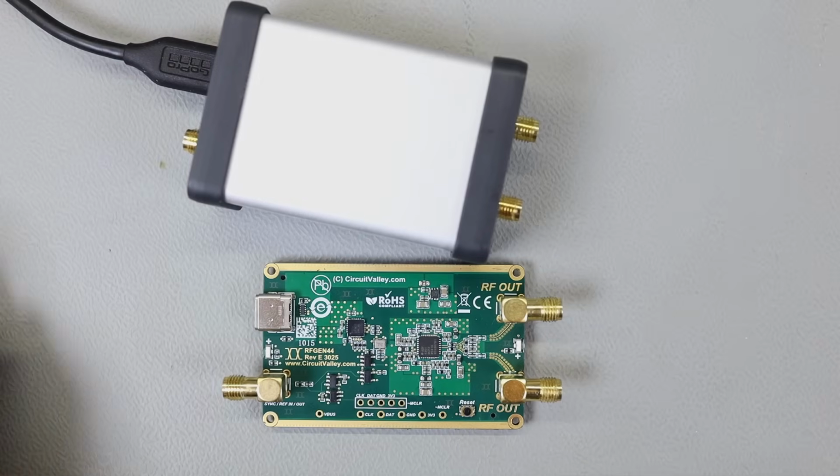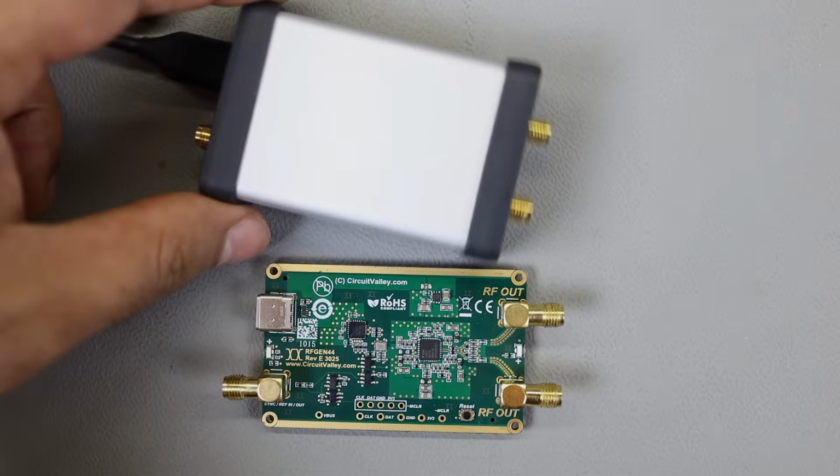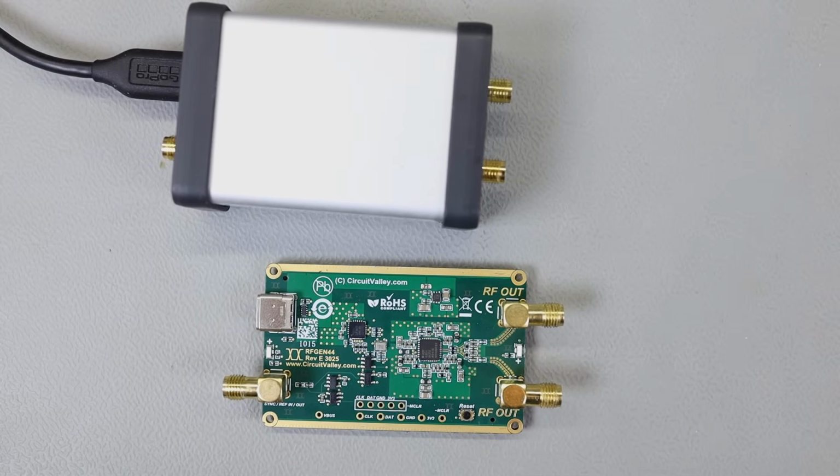So you can program the device to follow some steps, for example, set a frequency, wait n number of times, and then again turn on the output, turn off the output, set a frequency, or whatever you want to program. There are various ways you can program the macros, and of course standard features are still supported. You can do sweep, you can do hopping, you can of course do various other parameter programming.